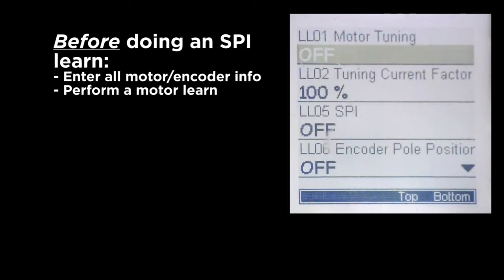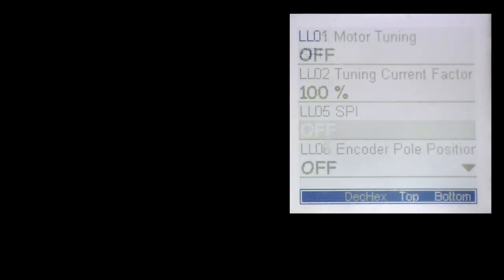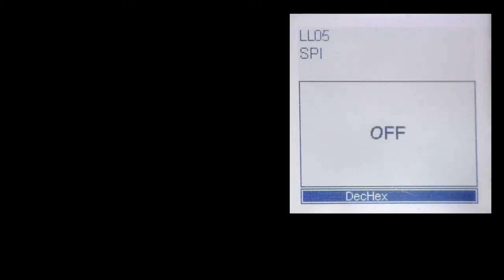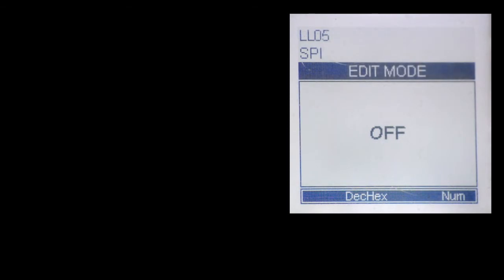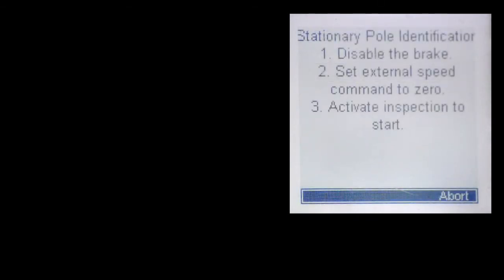From there, go to the programming menu and scroll down to the tune parameters, then go to LL05 SPI. Set that parameter to start and press enter, and then the basic overview of the steps will be displayed.